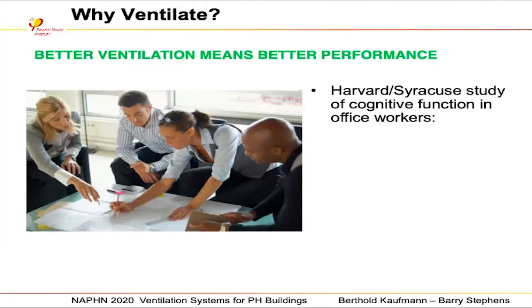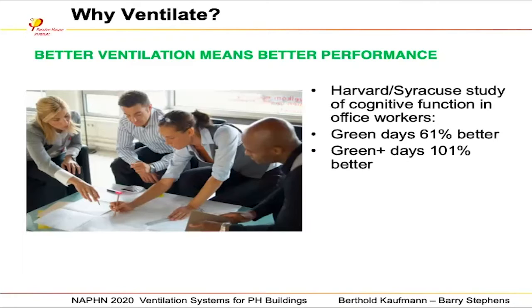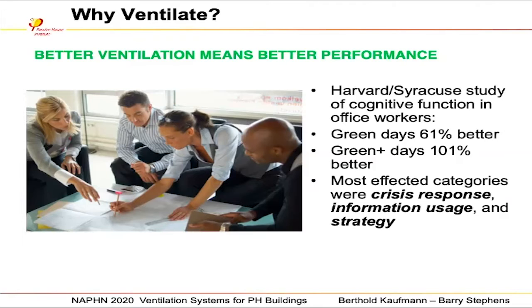There's a study at the Harvard School of Public Health, done at the Syracuse Center of Excellence. It was a double-blind study based on CO2 levels, which really represented ventilation rates. And what they found was on a green day, which is reducing CO2 levels from approximately 1,200 parts per million to 800 to 900 parts per million, cognitive function in a double-blind study increased by 61%. The green plus day, which is represented by 600 to 700 parts per million, is 101% better cognitive function. And the most affected categories of cognitive function were crisis response, information usage, and strategy.